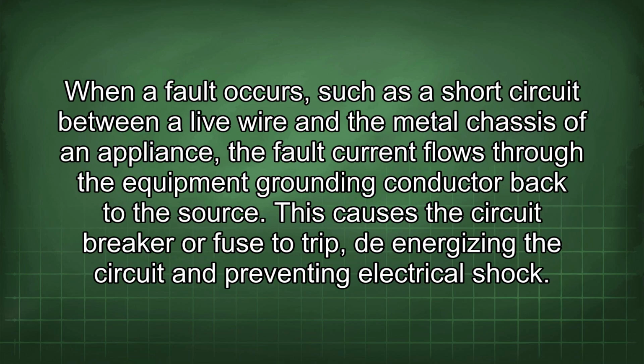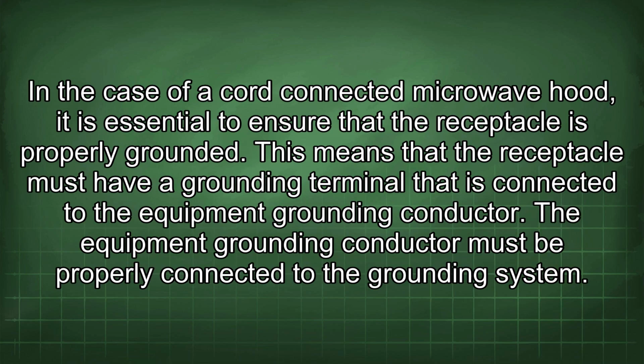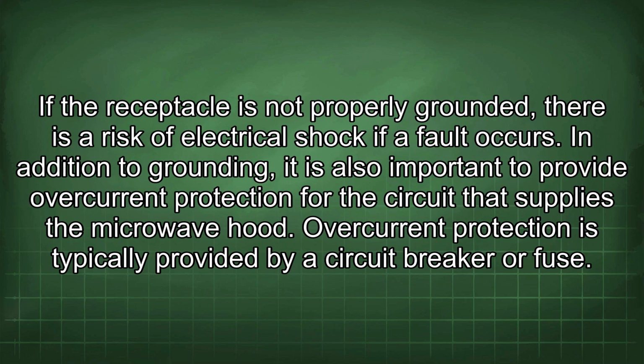When a fault occurs, such as a short circuit between a live wire and the metal chassis of an appliance, the fault current flows through the equipment grounding conductor back to the source. This causes the circuit breaker or fuse to trip, de-energizing the circuit and preventing electrical shock. In the case of a cord-connected microwave hood, it is essential to ensure that the receptacle is properly grounded. This means that the receptacle must have a grounding terminal that is connected to the equipment grounding conductor. The equipment grounding conductor must be properly connected to the grounding system. If the receptacle is not properly grounded, there is a risk of electrical shock if a fault occurs.